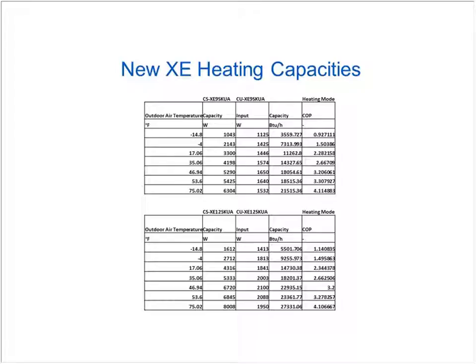One of the things I wanted to show you here was that on this XE, this is a minus 15 degree application. However, at minus 14.8 tested, your COP over here to the right is less than 1. And basically electric resistance heat is a COP of 1. So quite frankly, at minus 14 degrees, you're financially better off going to electric resistance heat. Even though the ductless heat pump will go that low, you're technically losing money by using a ductless heat pump at minus 14 degrees because the COP is below 1. And then the other thing you'll see is the BTU output drop out. So 3,500 BTUs, you're probably seeing a heat load requiring considerably more than that at that temperature.